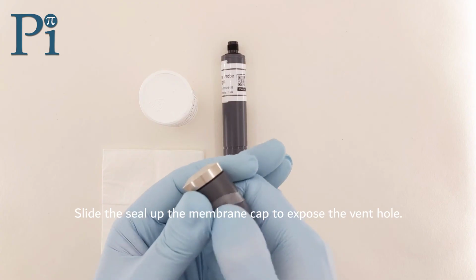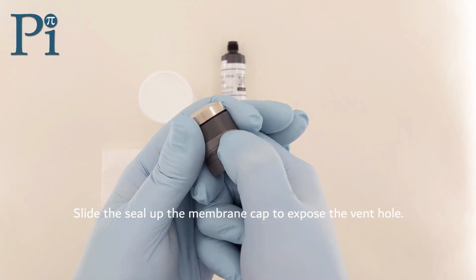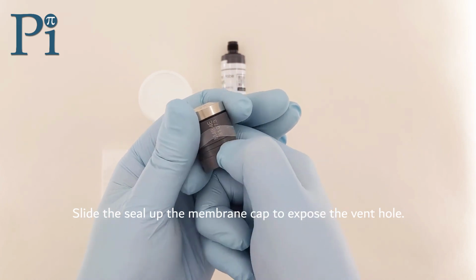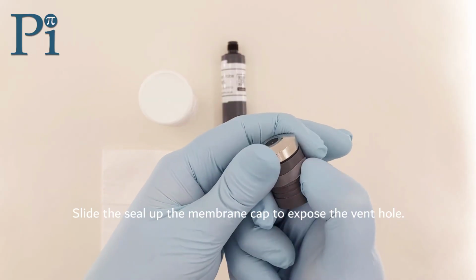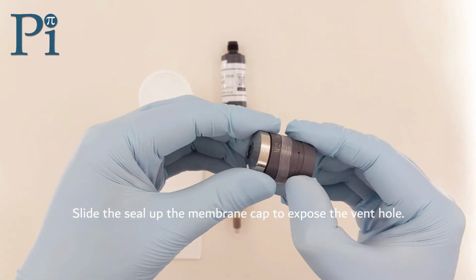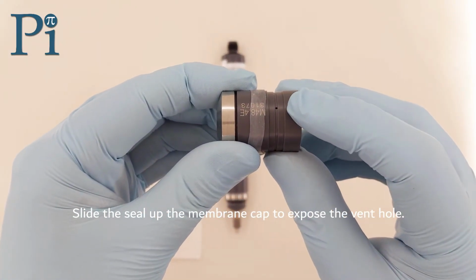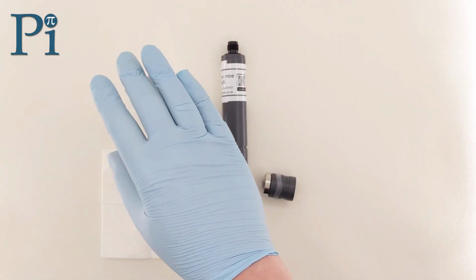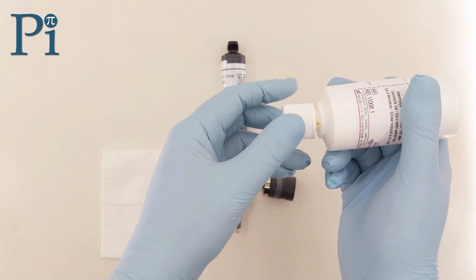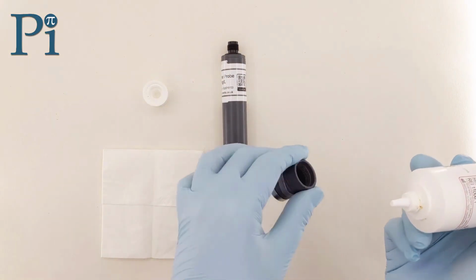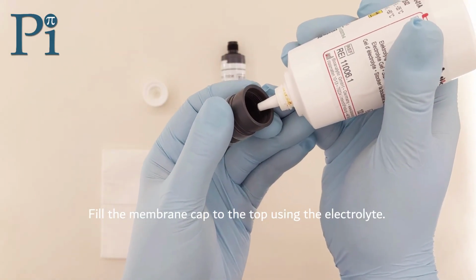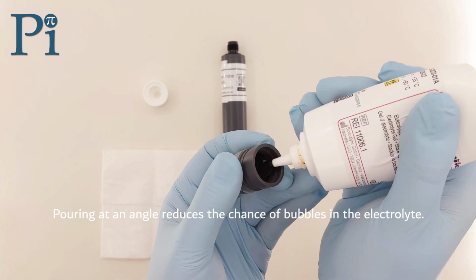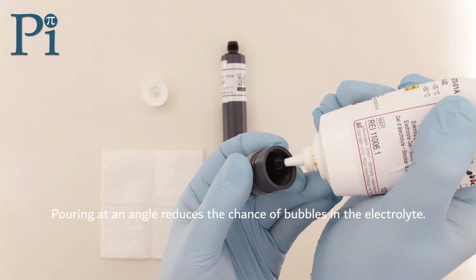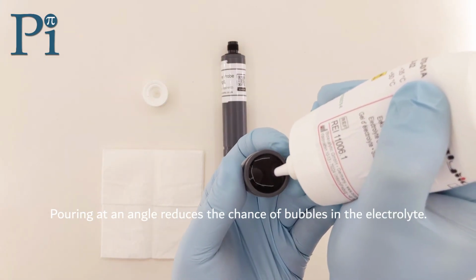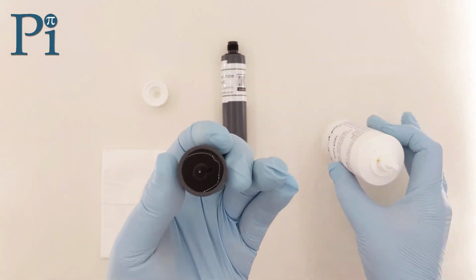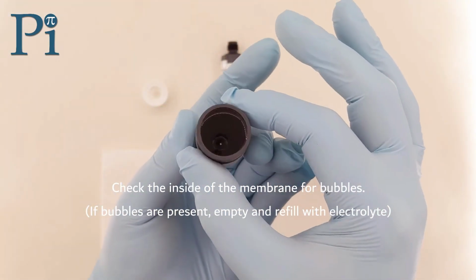Slide the seal up the membrane cap to expose the vent hole. Fill the membrane cap to the top using the electrolyte. Pouring at an angle reduces the chance of bubbles in the electrolyte. Check the inside of the membrane for bubbles.